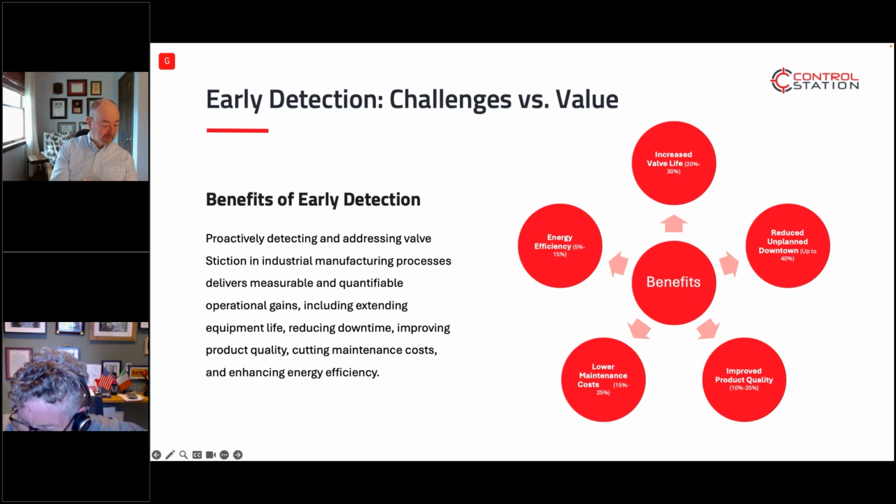Yeah, the oscillation is key to that. It's something that people take for granted, particularly with new plant, new equipment, that these valves have 1 million cycles in them. We can run these, but it's the wear and tear that you build up in that first 18 months of perfect operation that is going to start showing up further down the road, through aggressive tunings, through lack of maintenance. We just spent millions on this plant, we're not going to have our maintenance budget stressed for the first phase of this. All of these things will feed down the road into that process.